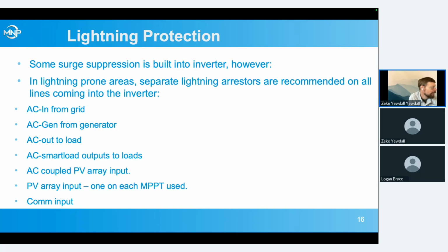you want to have surge suppression on that as well, especially if you've got, say, a remote equipment shed and you're running internet out to it for monitoring. Best practice is to actually run fiber and use little converters on each end rather than copper Cat5 if you're in a lightning prone area.